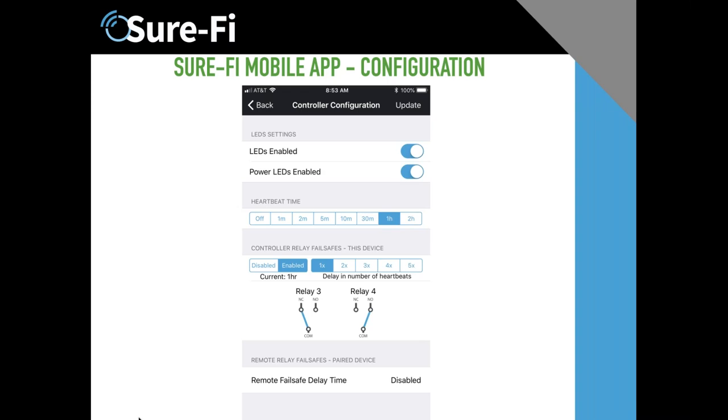So if you want door one to be on relay one, door two to be relay two, door three to be relay three, door four, et cetera, then you can differentiate it with one to many, but it's not really a true multi-point because it's not receiving that Wiegand data back. This is relay only and is differentiated with wiring instead of using a self-addressing type of application. I hope that answered the question.